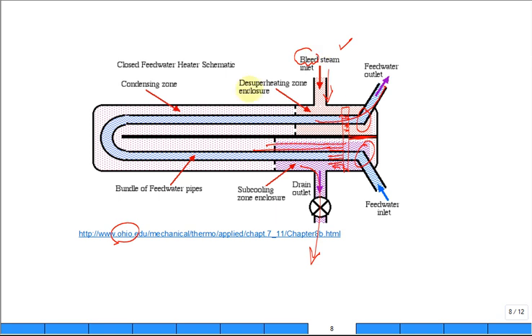They have a zone where it's desuperheating. Engineers can make up all kinds of words, right? Desuperheating, you can't find it in Webster's, but the steam is superheated in that region. It's going to be cooled until it flows to this region, where it's now going to be condensing. Then it flows on the outside of the tubes. Typically there's baffles to force it to swish around. It's condensing, and it's collecting droplets at the bottom. Then it'll have a zone after it's condensed where it's subcooling. In our analysis, we take out saturated liquid, not subcooled liquid.